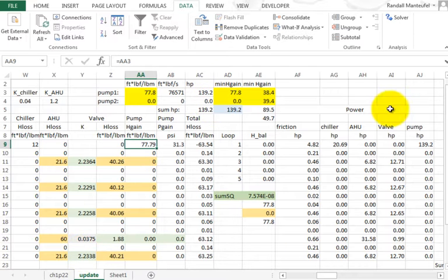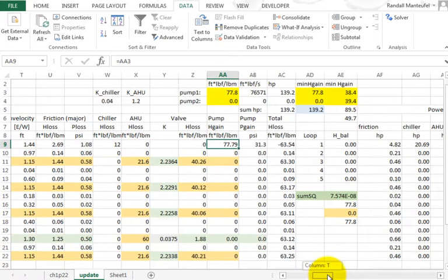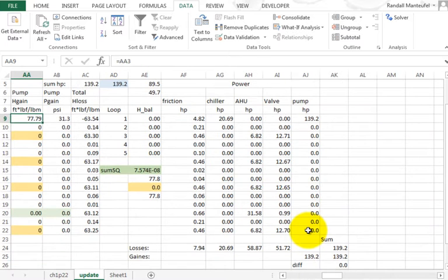Okay, you can look at powers in different parts, where the power goes. Let me see if I could show the power here. In valves, that's about the 50 that was lost. I know that if this one valve is open on the floor, it's about 1 horsepower continuously lost in that one valve. So it's about 50 horsepower that's lost above the partially closed valves.